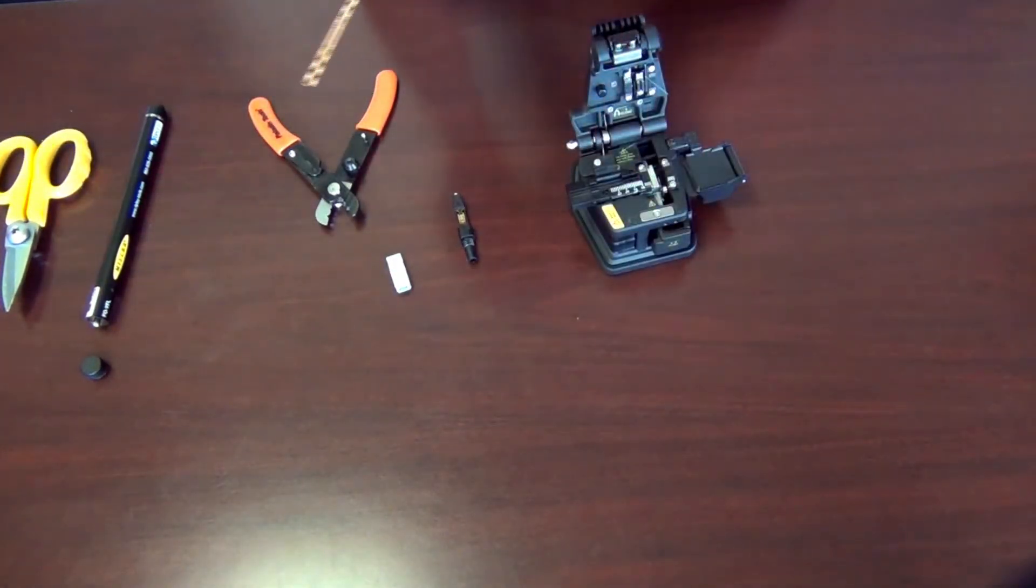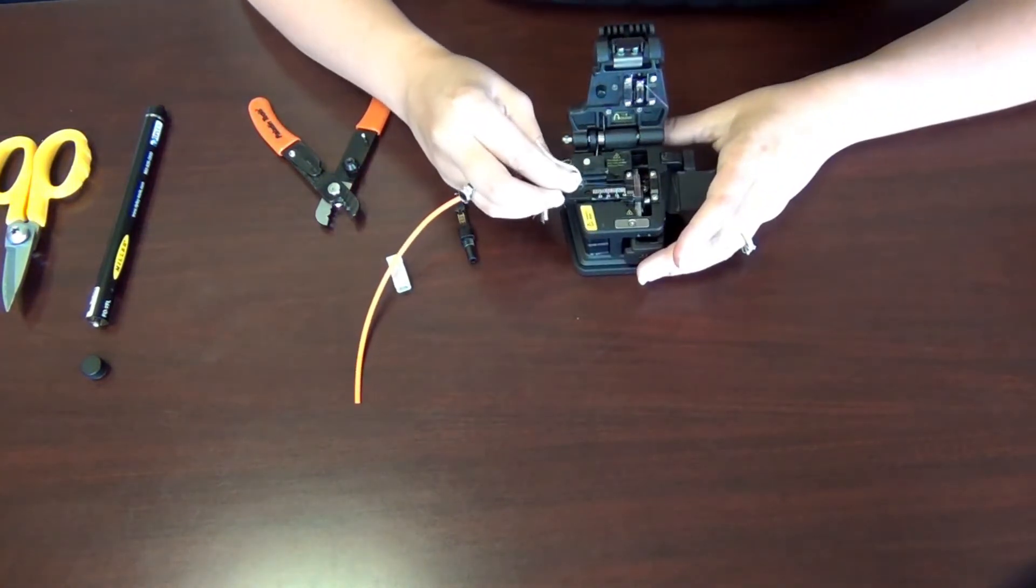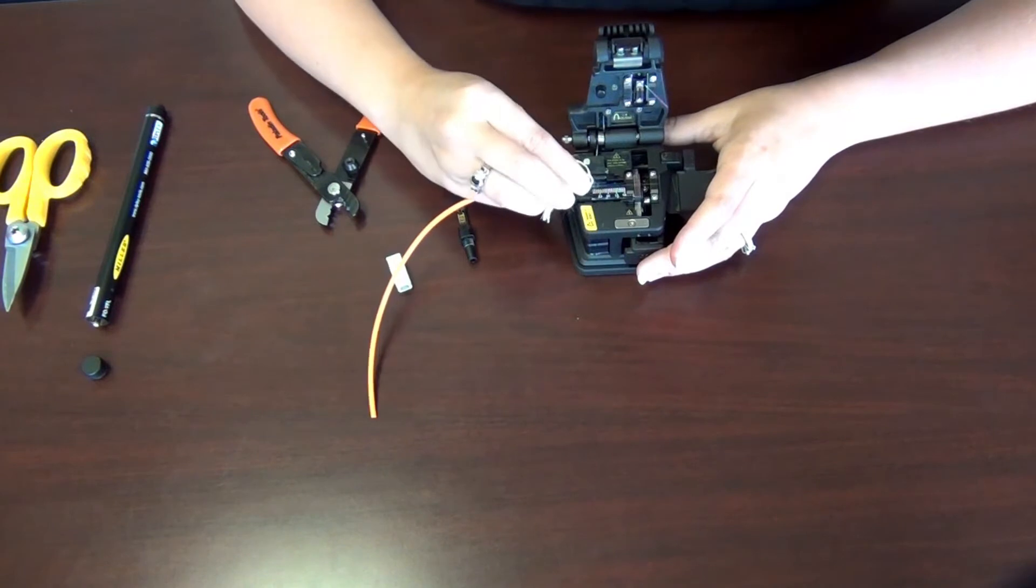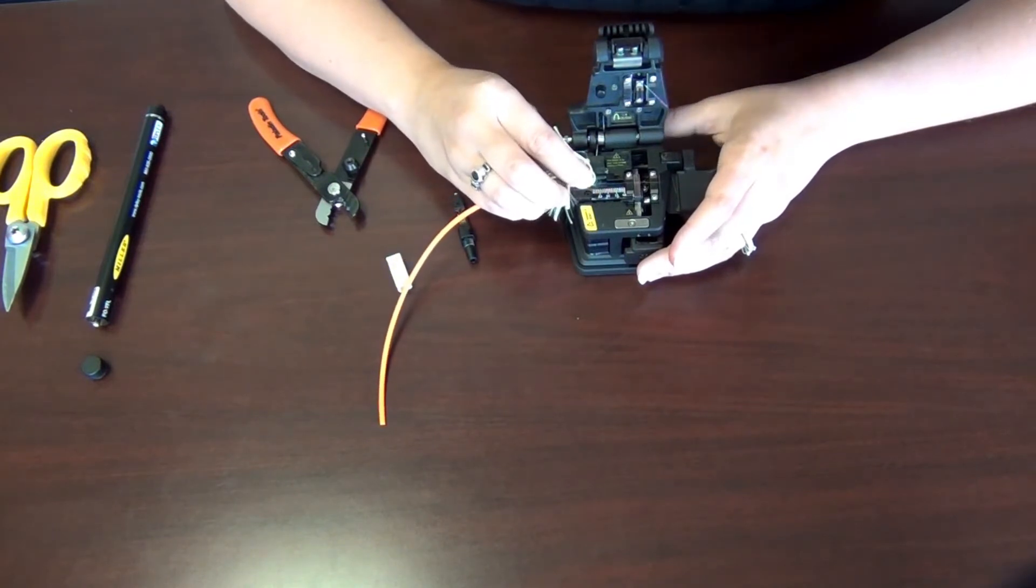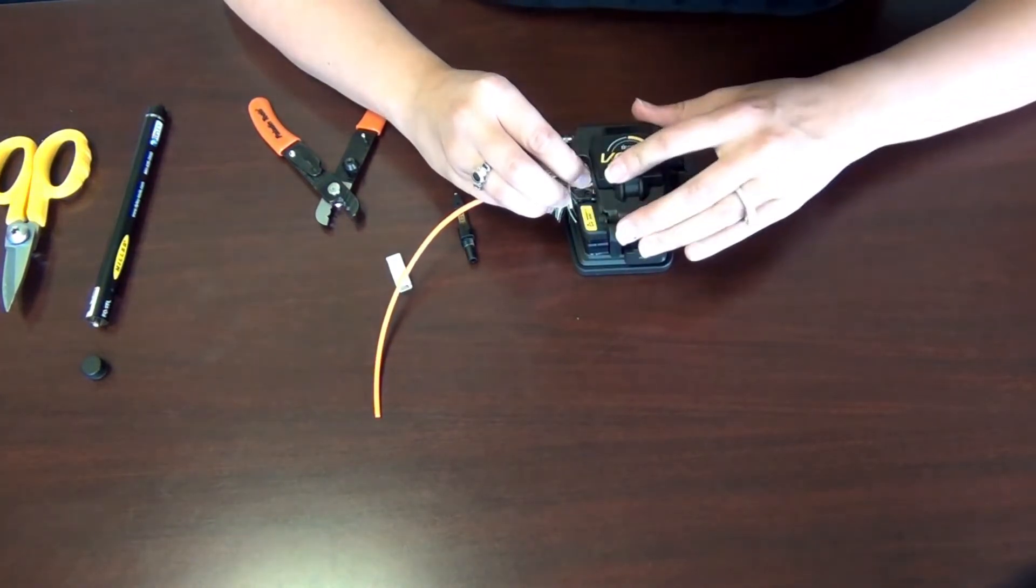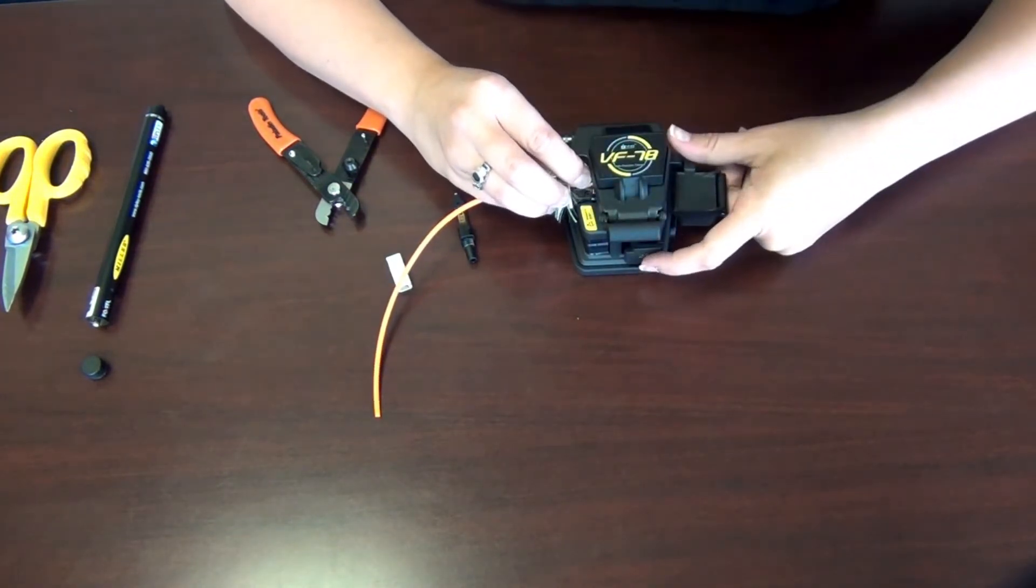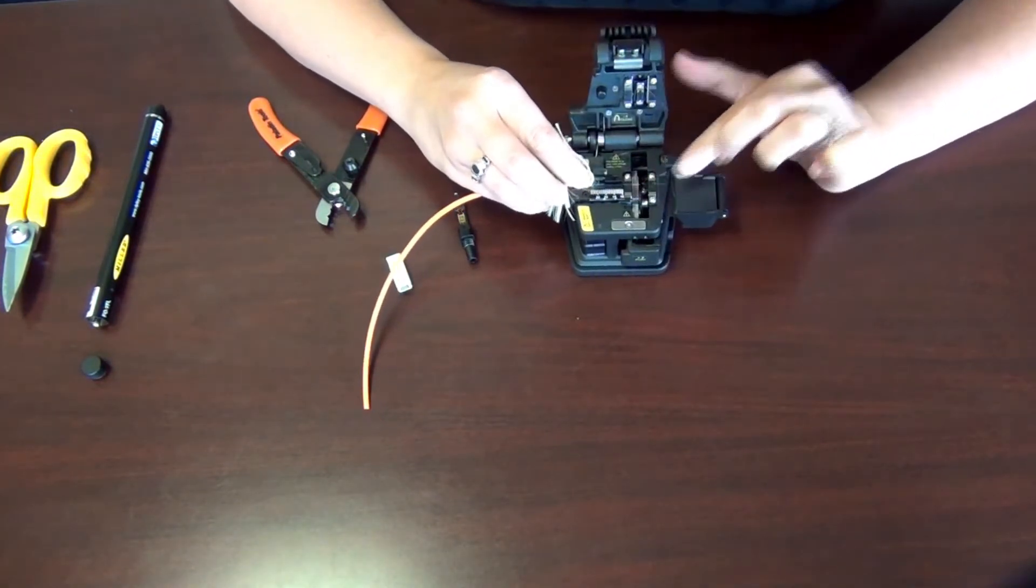Now we're going to cut it to the right length. This cutter also came with the clear line termination kit. We're just going to fit it right in here. You want to make sure that your wire lines up to about 28 millimeters. It's going to make sure that it's the right length to go in the connector. Just snap this down and push this button back and it's cut.